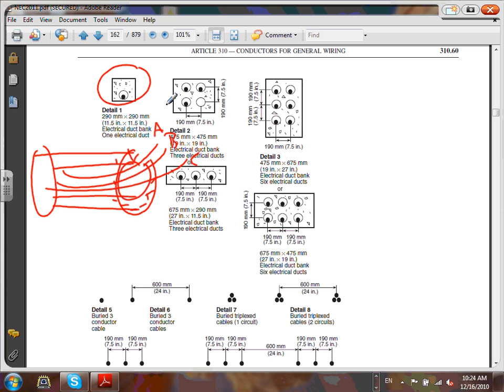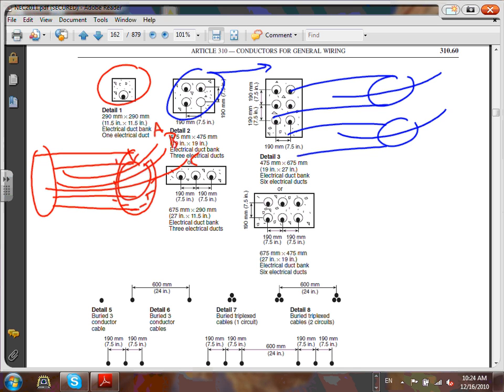You can use detail number 2, where you can put them in 3 single conductor cables. This guy here, you can use it as, here's my cable, one cable, basically one cable. Does it make sense? One cable and one duct. Where would I use this 1 versus 2? If your cable is huge, you can't fit it in one duct. Multi-conductor cable. Imagine these. What was the size? Our size was 4-aught. That's small. What if I need 500 kcm medium voltage? You can't.